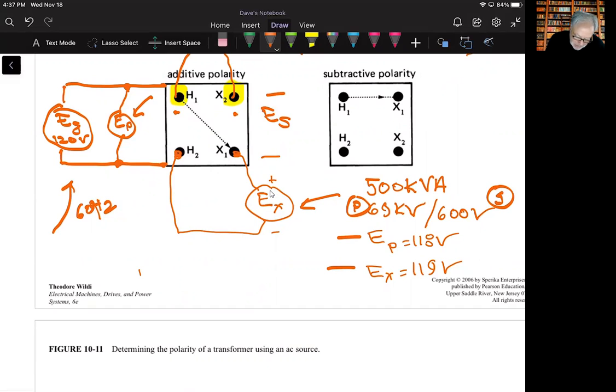He goes on to say that the high voltage and low voltage terminals connected by the jumper must be respectively labeled H1, X2. Since additive would be in this direction, we've determined it is additive, so that means we'd label that as H1 and that as X2. We would know that.